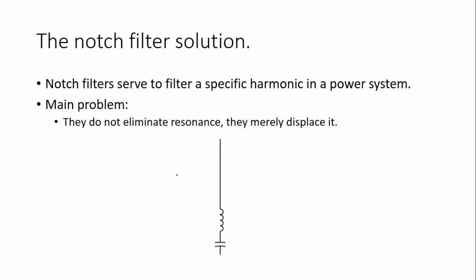Now, normally, when we have harmonic content in a system, the most popular and cheapest solution is the notch filter. When you want to filter a harmonic from a system, you may install a passive filter, which is the most popular and cheapest way to free harmonic content from a system. That filter will drain the tuned harmonic to the ground. Let's say this is a fifth harmonic filter, which is very popular. All the fifth harmonic current will flow through here to the ground and will not dwell in the system. It will not cause distortion in the system impedance.